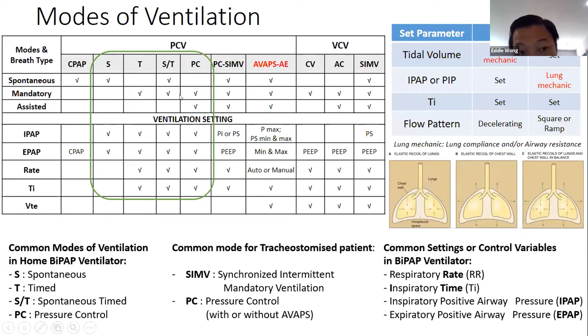So how the breath is delivered: if the breath is mandatory breath, if I go back here, you see the mandatory, all the modes here, ST or pressure control mandatory, meaning the machine or the doctor or the care provider will set these two settings inside the machine called respiratory rate and I time. So if the rate is 10 breaths per minute, you know 1 minute is 60 seconds, right? If your rate setting is 10, 60 seconds divided by 10, which means every 6 seconds, mandatory, the machine will deliver 1 breath to help you to breathe.